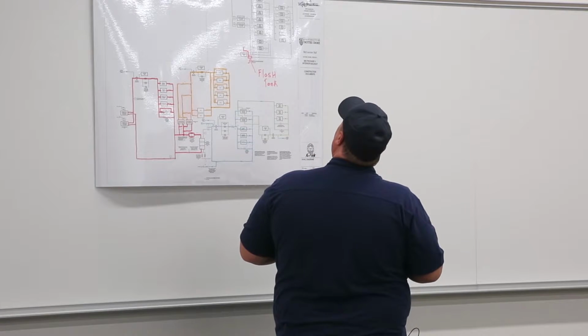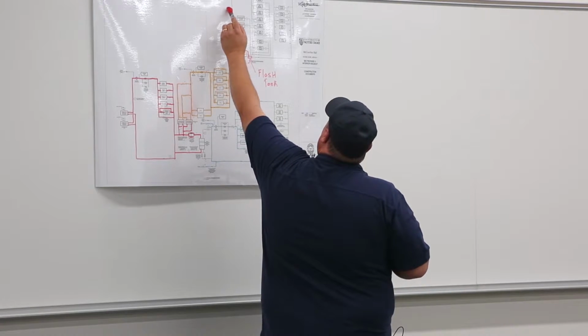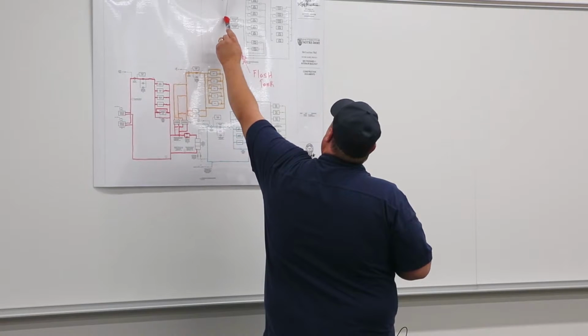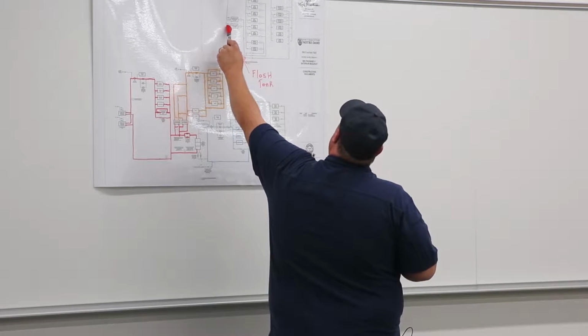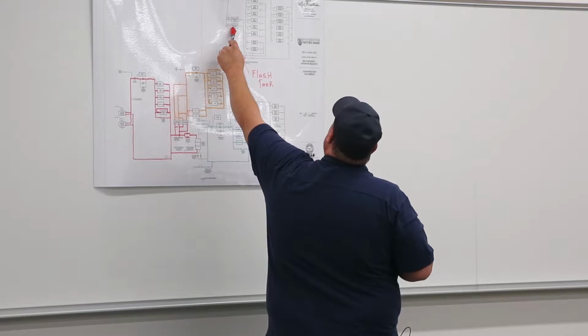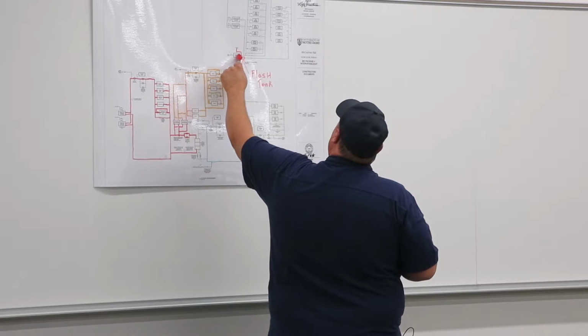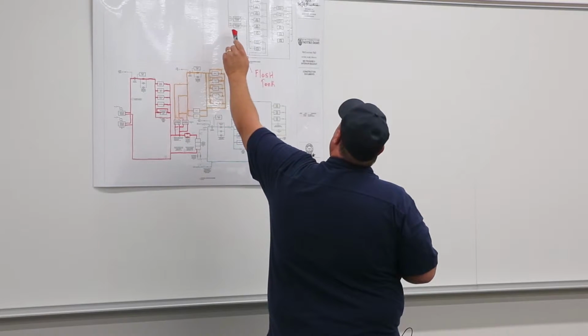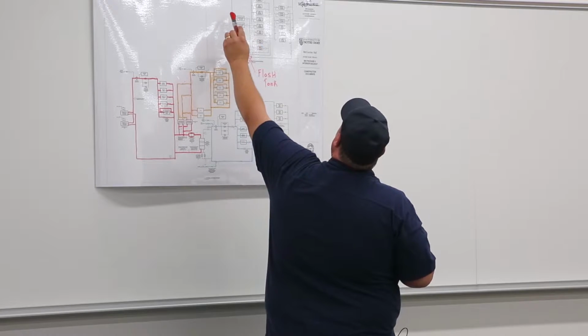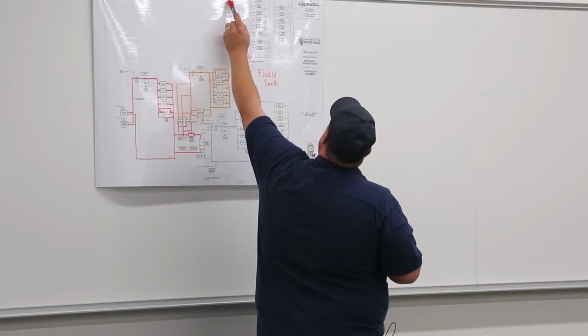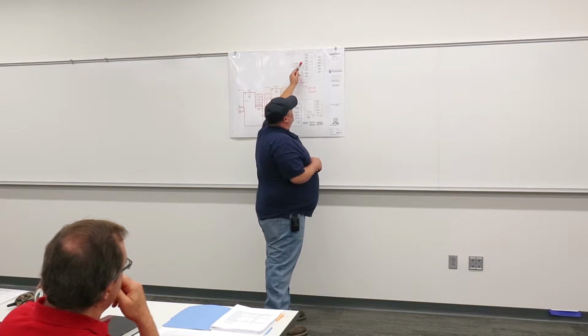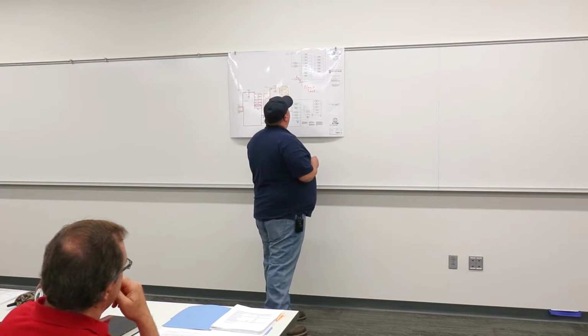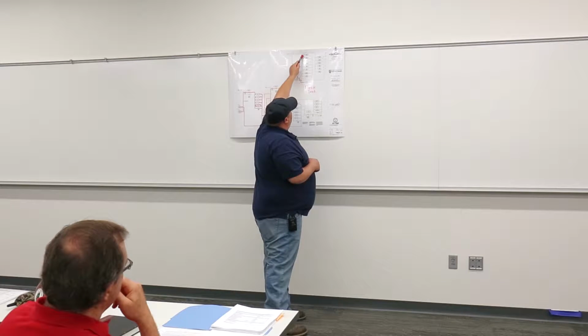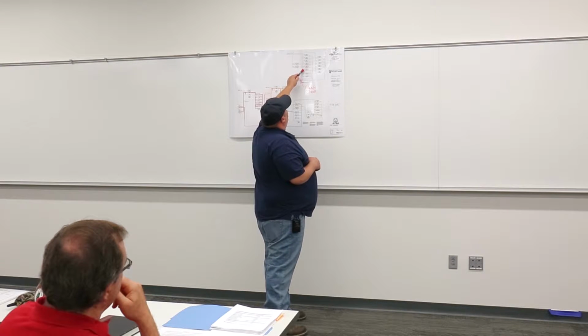The low pressure steam comes in from the plant. It goes to a valve station located in the lower level mechanic room that feeds our heating hot water heat exchangers. From that point, it returns back to our condensate receiver pump, and that's the gist of all of our low pressure steam in the lower level basement mechanic room. It also proceeds on up through the building, up to the penthouse. As it proceeds through the penthouse, it goes up to feed the several humidifiers on our 6 air handler units throughout the building, up in the penthouse.